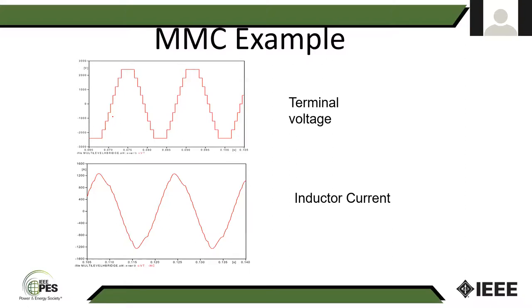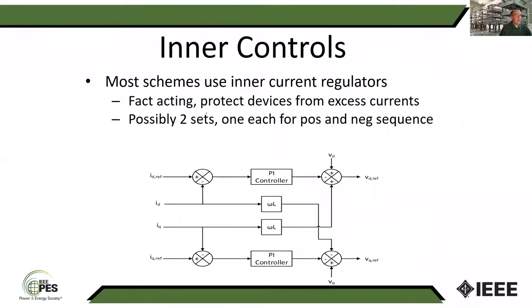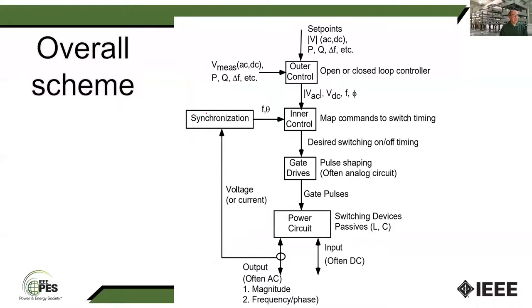Okay, so one question was, how voltage ride-through fits in the control loops? When we talk about voltage ride-through, that's really going to be for especially transmission applications, and there's a question of where that fits in for inverter controls for microgrids. But low voltage ride-through comes back to when you started to see increased penetration of large wind installations on the transmission system in several parts of the world. It came up all at about the same time, that if you had an AC system fault and that caused a voltage sag, the converter controls were shutting off the wind turbines. Or if it was something like the early type 1 and type 2 wind turbines, they may just shut off because the voltage got too low.